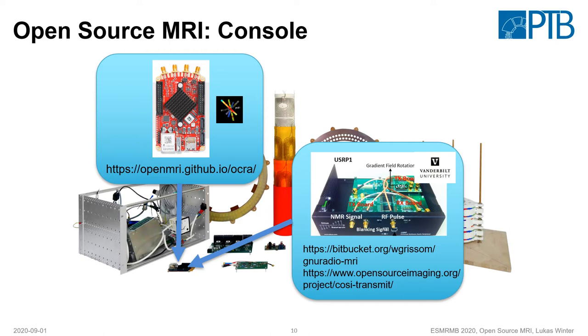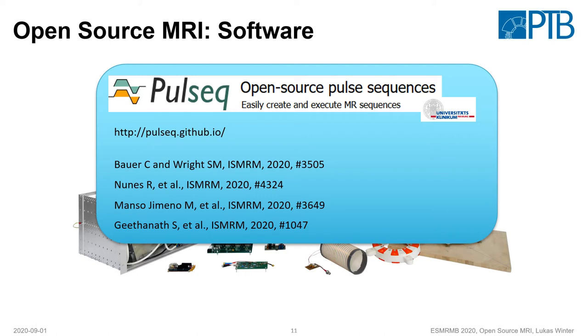For the console we can use a Red Pitaya to play out the pulses and receive a signal — this is by the MIT MGH group, provided with code named OCRA. Another approach is using a GNU radio compatible software designed to play out MR pulse sequences, from Vanderbilt University. For hardware-independent MR pulse sequence development we could use tools such as Pulseq coming from Freiburg, which allows us to do pulse sequence development and hardware development in parallel.